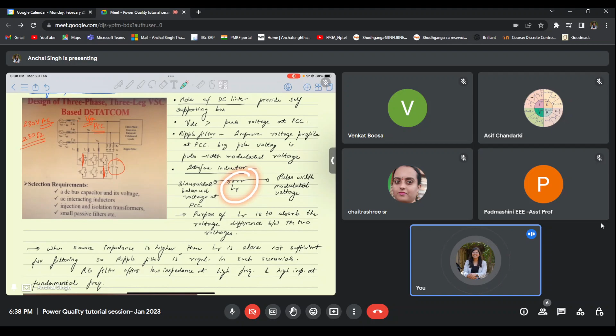So when you look at the DC bus voltage, this formula came from the fact that when the line-to-line voltage is given for a three-phase system, the phase voltage is obtained as line to line by √3, right? Phase voltage is equal to line-to-line voltage by √3. Now, in order to calculate the peak value of this phase voltage, I will multiply this phase voltage by √2. Okay, and then my VDC by 2 should be greater than or equal to the peak voltage at the point of common coupling. And why VDC by 2? Because let us consider a three leg converter. So in order to analyze this converter, we analyze it like this.